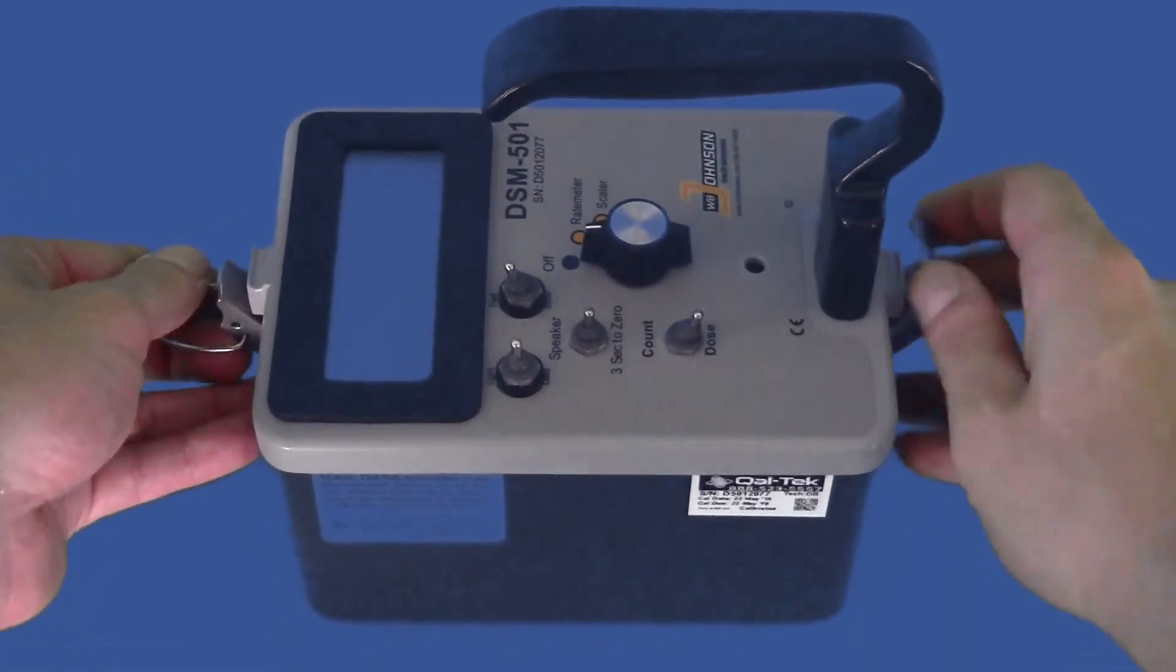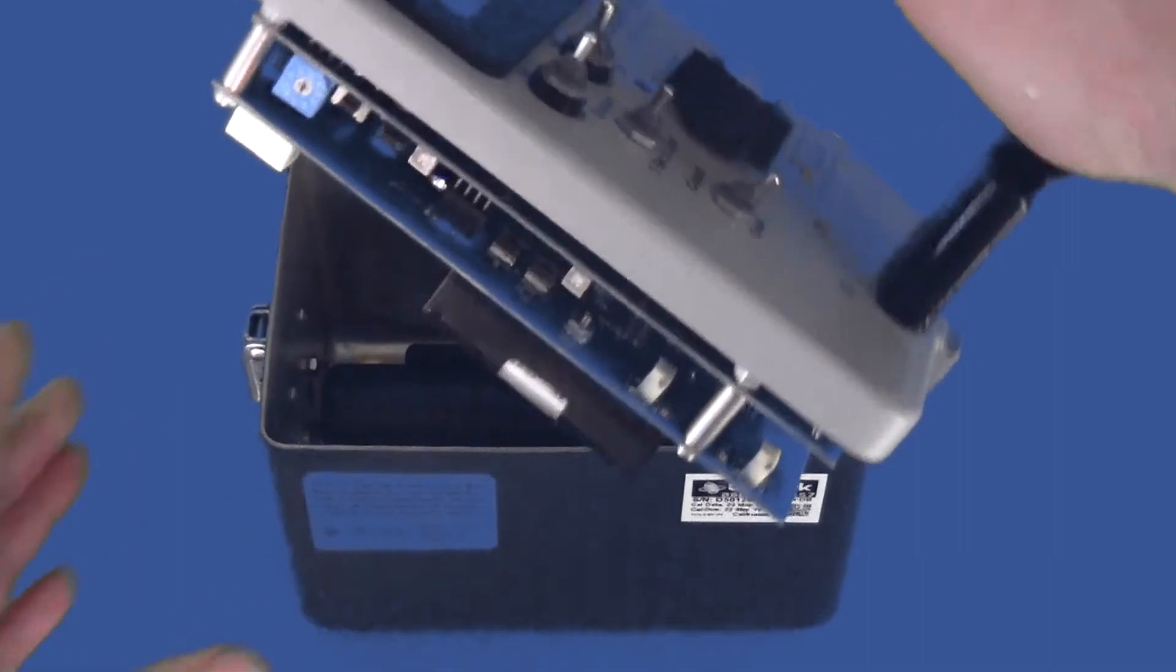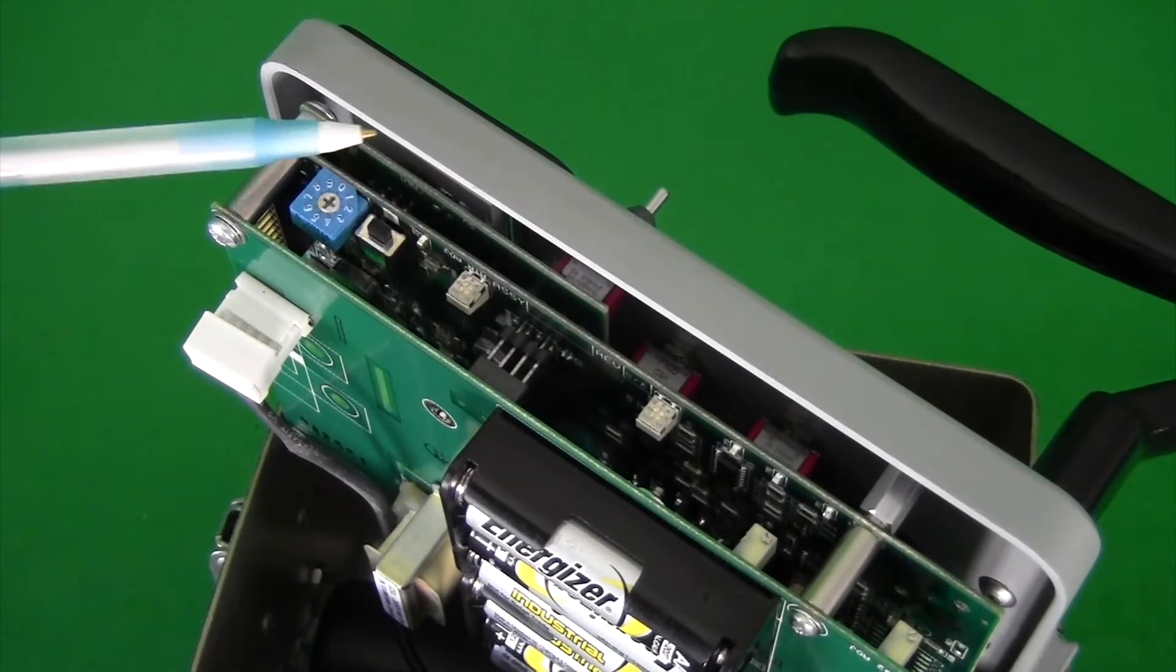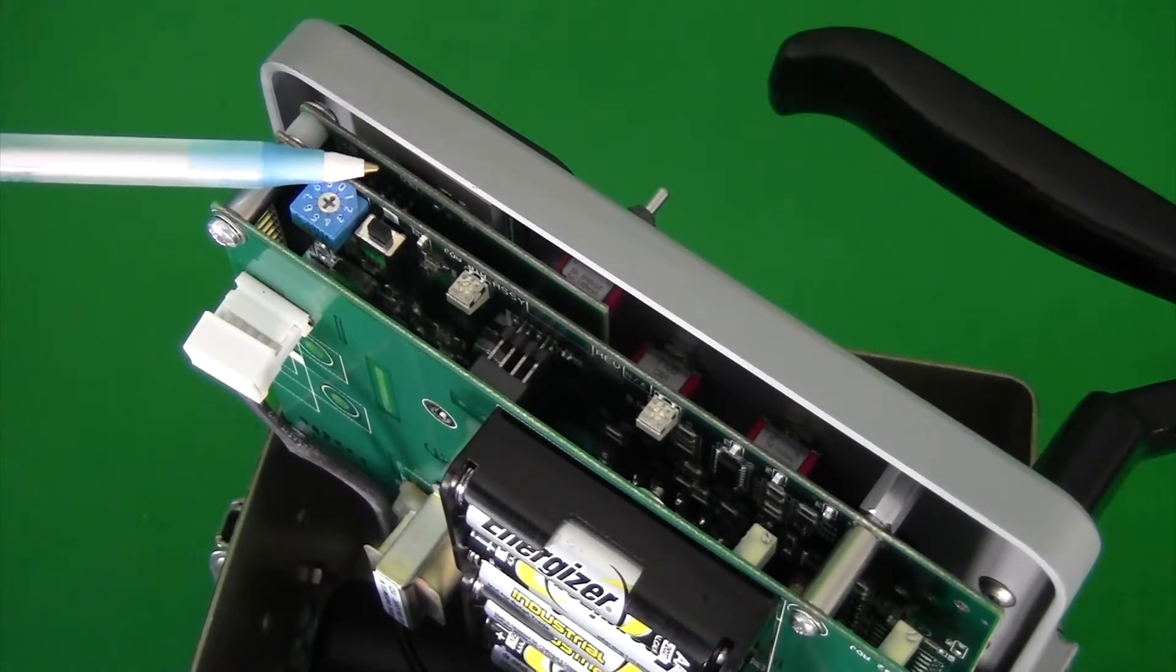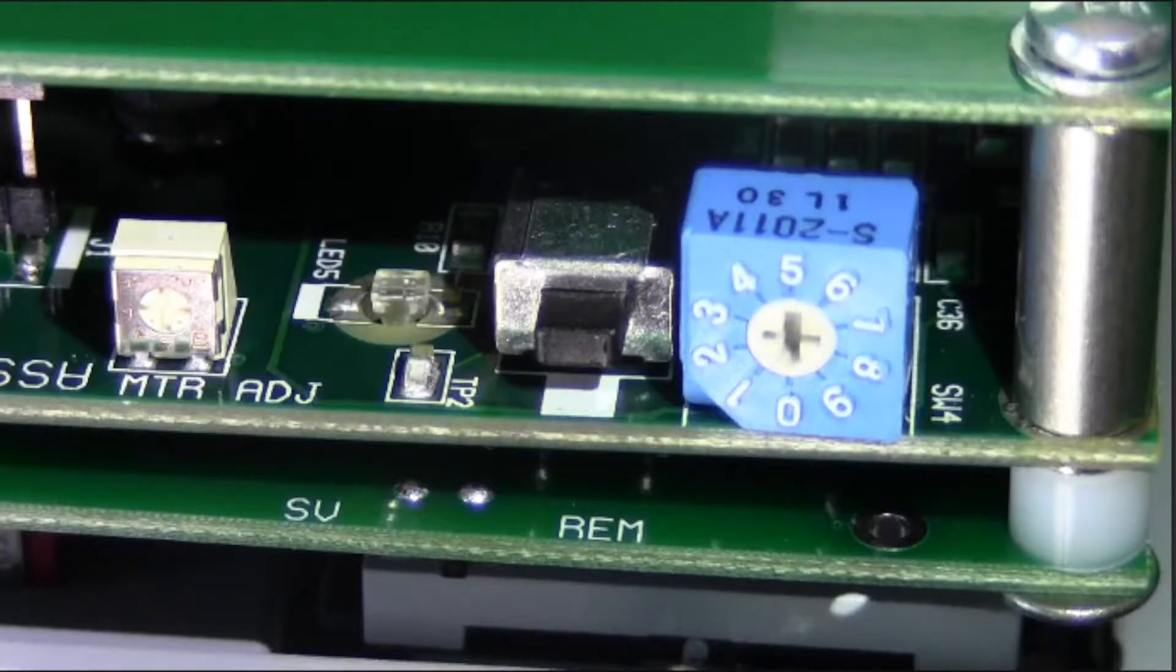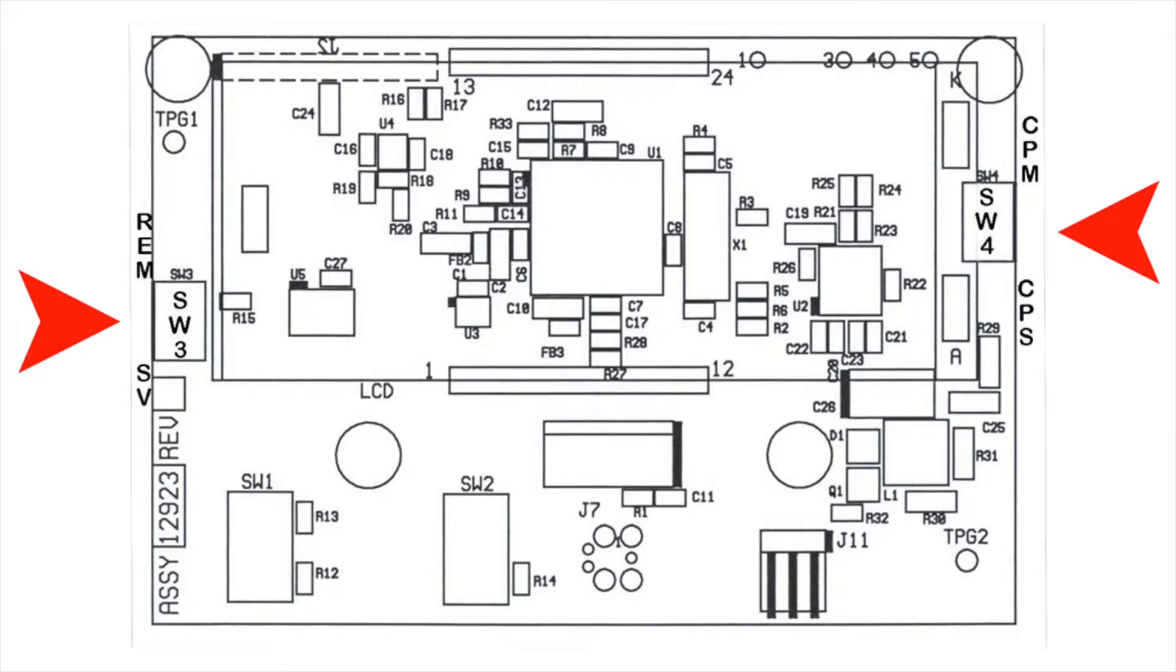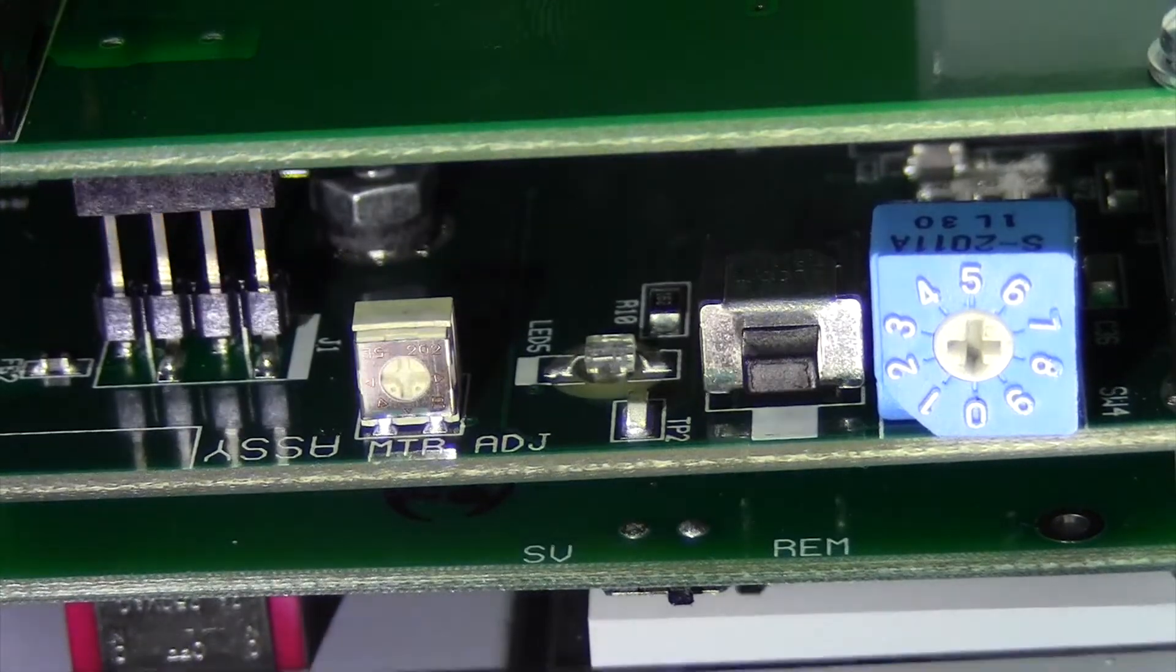The controls used to switch units of dose and counts are located on the LCD PC board. This is the circuit board closest to the display. If you look closely, you can see the markings. Sieverts to Rem and CPS to CPM. Both switches are clearly marked and located on opposite sides of the board from each other. Now switch units with a small screwdriver.